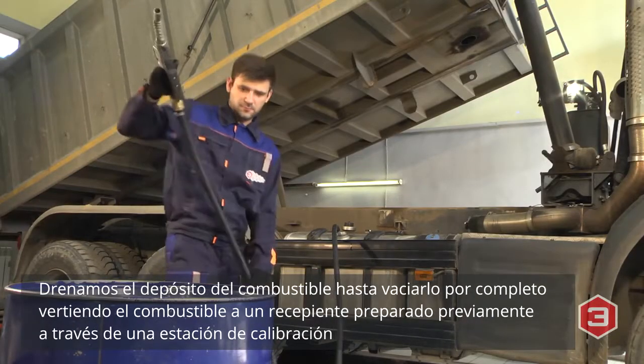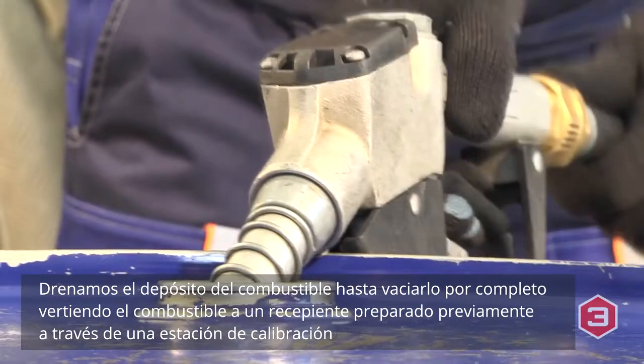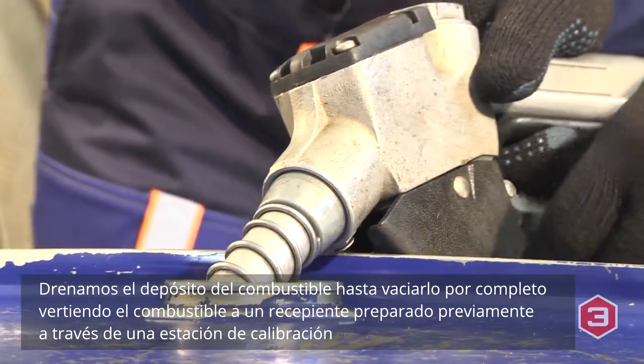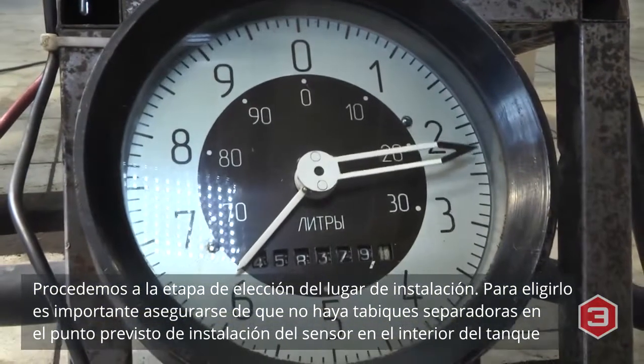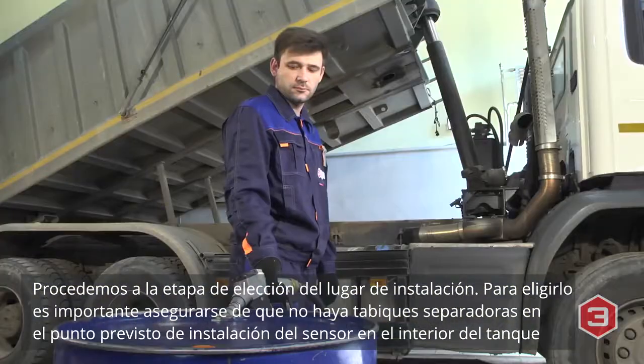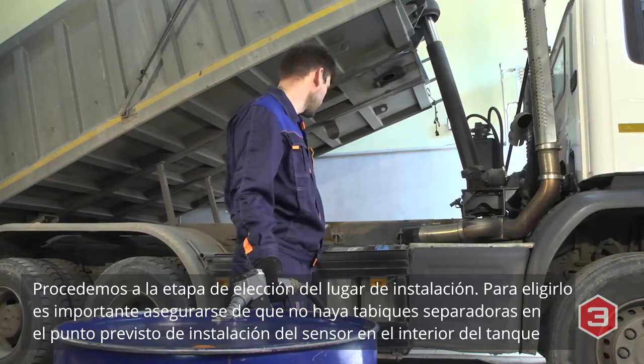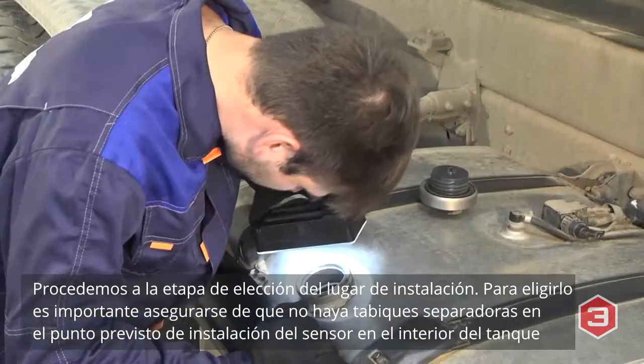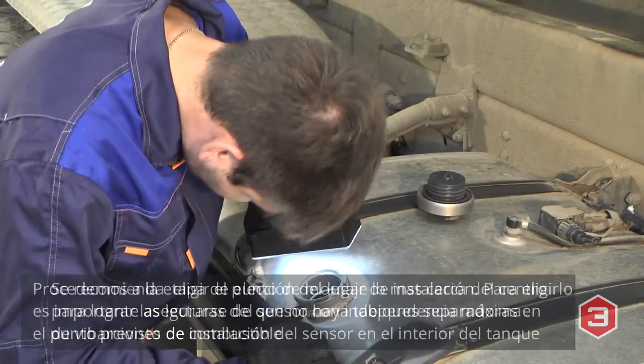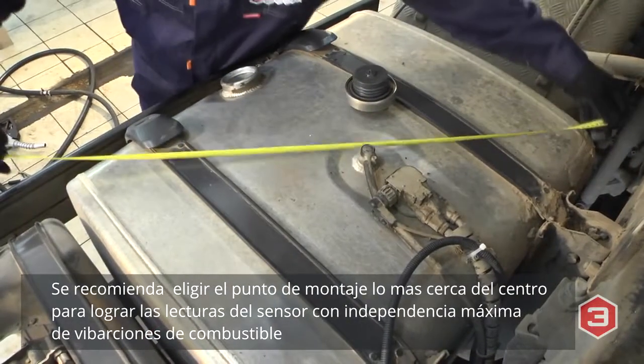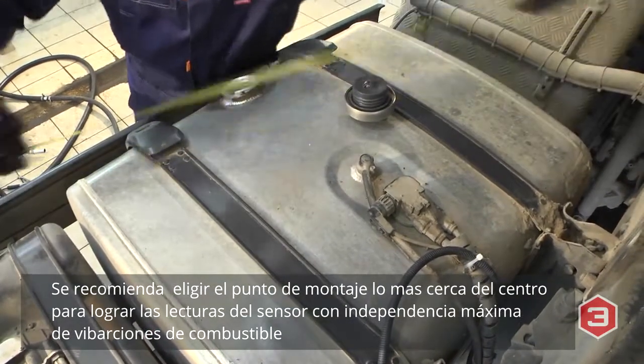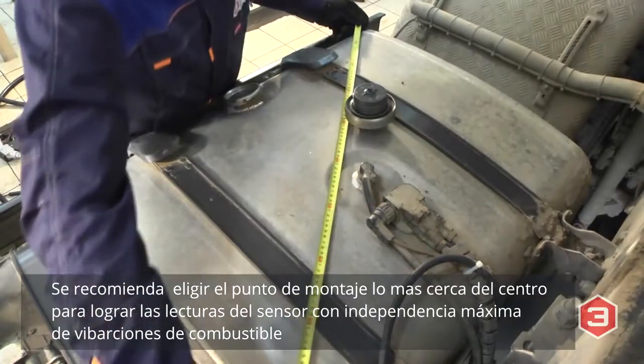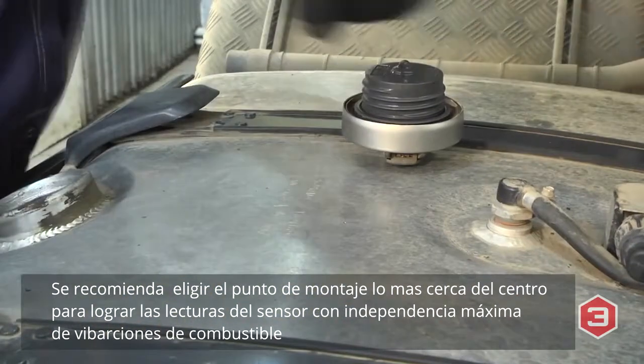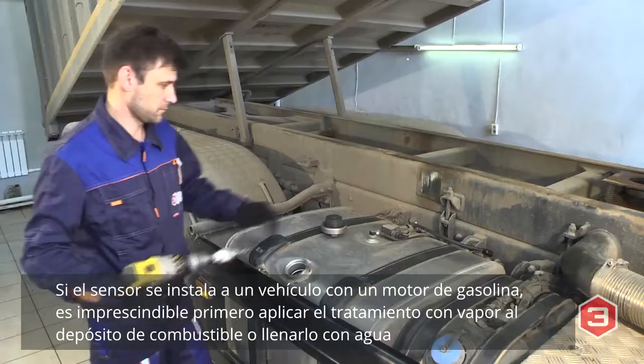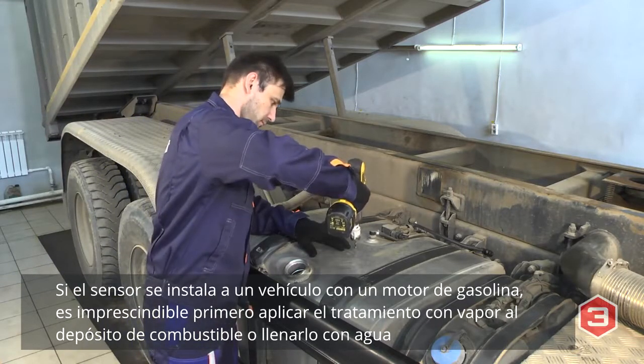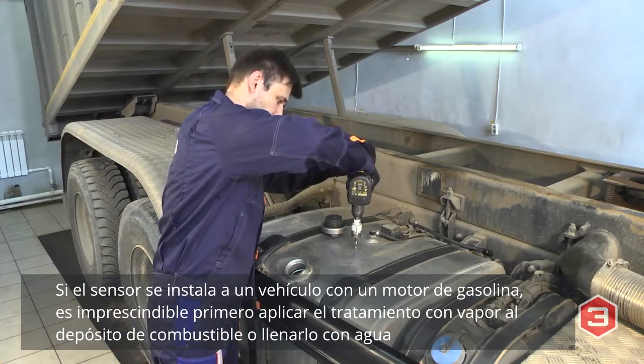Empty the fuel tank into a container prepared in advance using a fuel calibrator. Make sure there are no baffle plates inside the fuel tank before mounting the sensor. Choose the location as close to the center as possible, so that the sensor readings will be maximally independent of fuel fluctuations. If the sensor is mounted to a gasoline vehicle, evaporate fuel vapors or fill the tank with water.